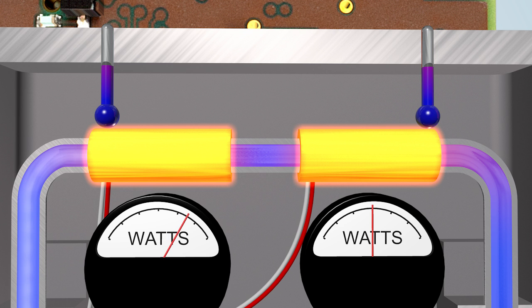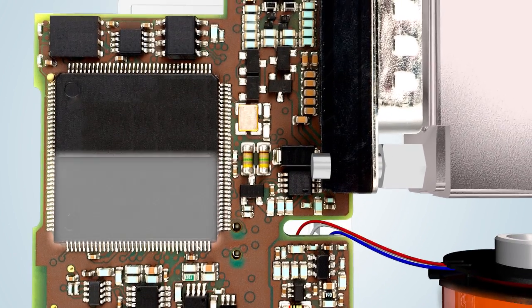The second winding sees that the gas has been warmed up, so the power to the second winding is decreased to maintain a constant average temperature over this winding. The power difference between the two windings is a direct measure for the mass flow.